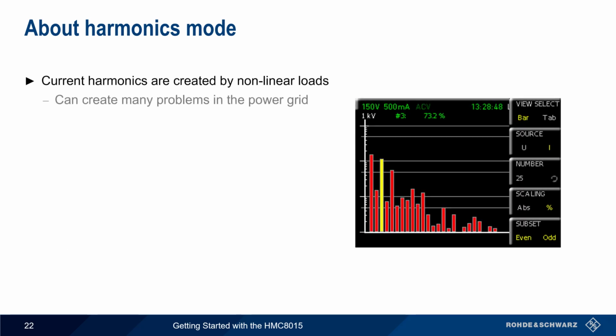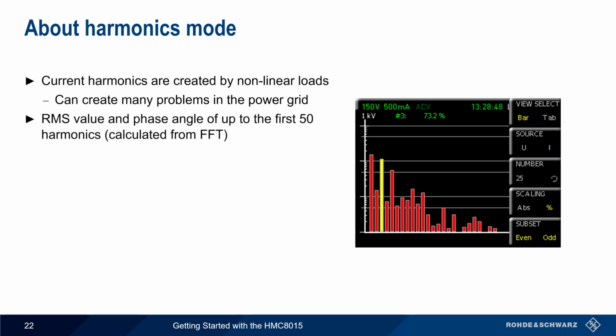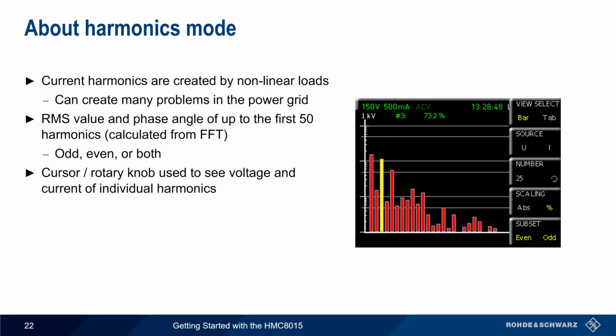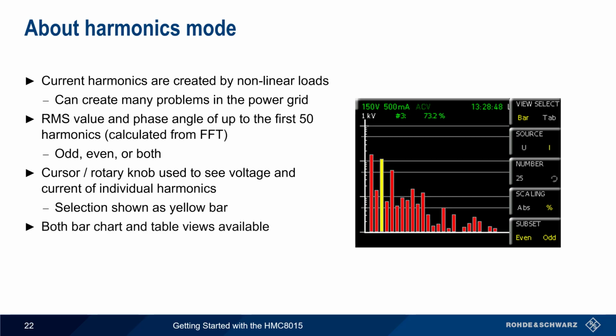The last standard measurement mode we'll look at is Harmonics mode. Harmonics are created by nonlinear loads and can create many problems in the power grid. Harmonic mode performs an FFT, or fast Fourier transform, in order to calculate the RMS value and phase angle of up to the first 50 harmonics. It's also possible to display only the odd or even harmonics. The cursors or rotary knob can be used to view the values for an individual harmonic, highlighted in yellow. In addition to the bar chart shown here, harmonics can also be viewed in table form, showing per harmonic magnitude and phase.